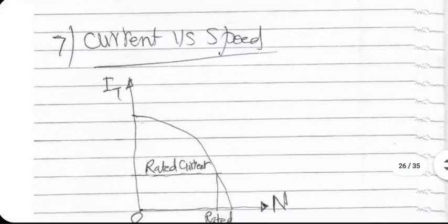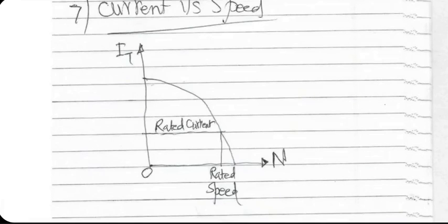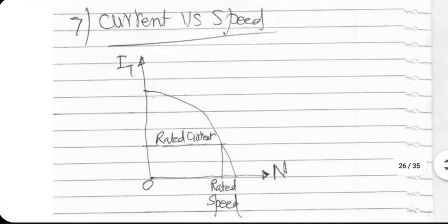Current versus speed: I have not proven it yet, but I'm giving you the basic idea right away. For an induction motor, the speed versus current behavior looks like this. The higher the speed, the lower the current that you can draw. There's a recommended range of operation, which is denoted by a rectangle here, beyond which you should normally not go.